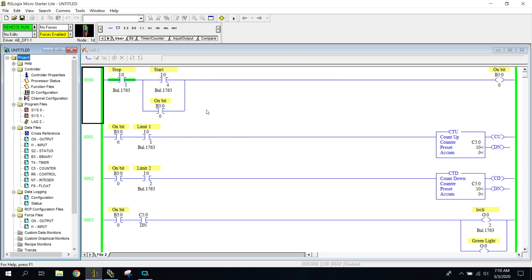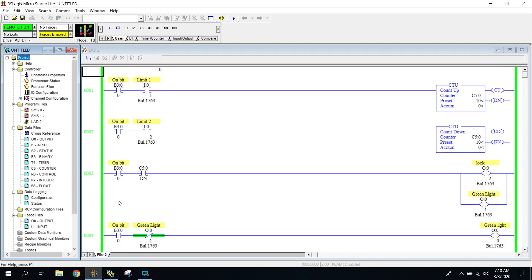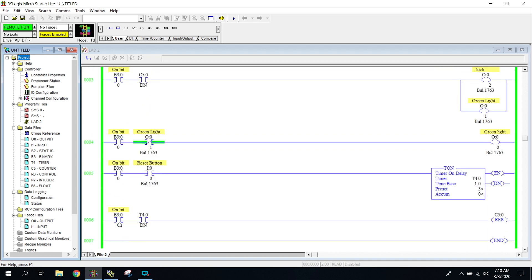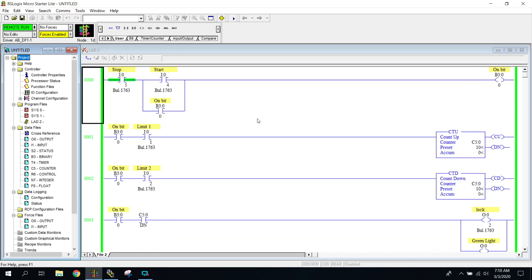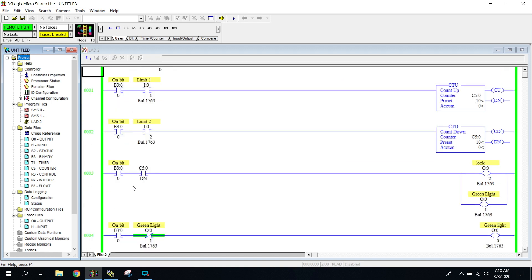Now I've used that same B3 bit in every rung all the way down this whole program. So what it's saying is, if this B3 bit is not energized here on this top rung, none of these rungs can become true, ever.